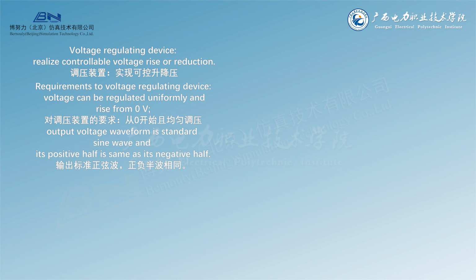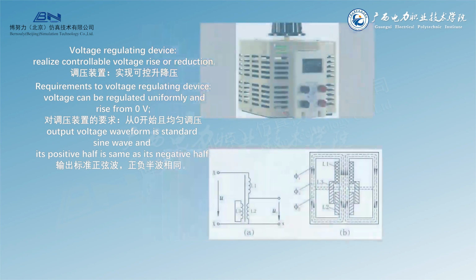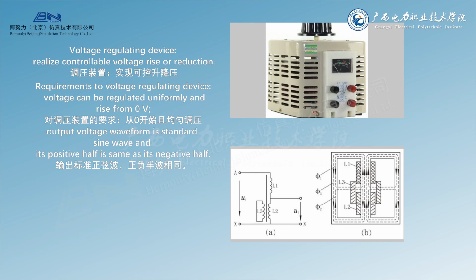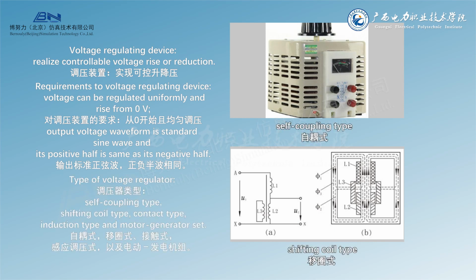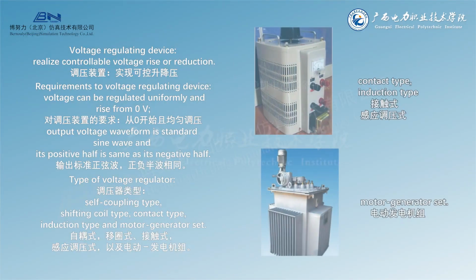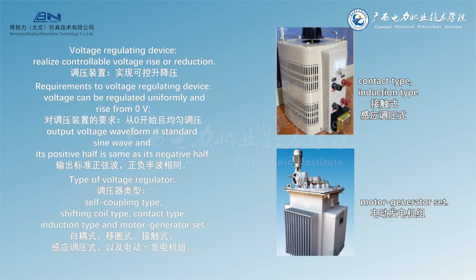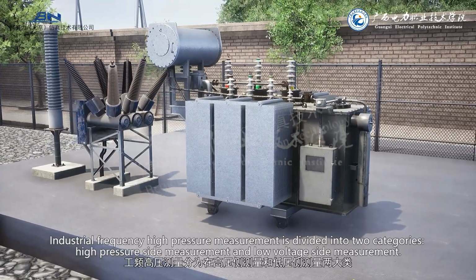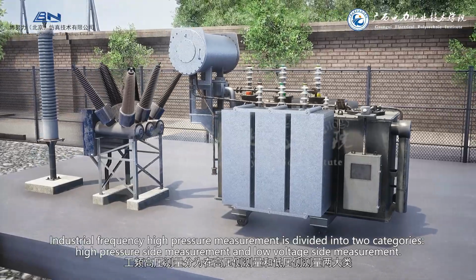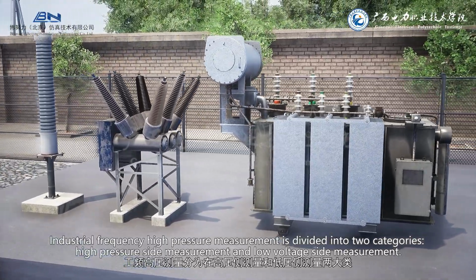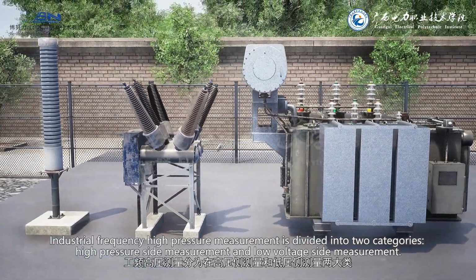Requirements for the voltage regulating device: voltage can be regulated uniformly and rise from 0 V. Output voltage waveform is a standard sine wave whose positive half is the same as its negative half. Types of voltage regulator: self-coupling type, shifting coil type, contact type, induction type and motor generator set. Industrial frequency high voltage measurement is divided into two categories: high voltage side measurement and low voltage side measurement.